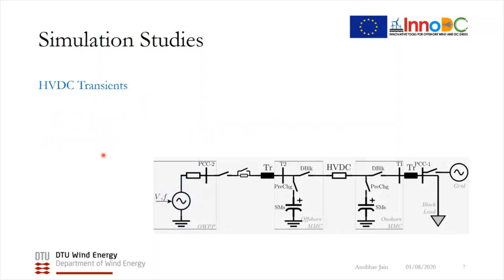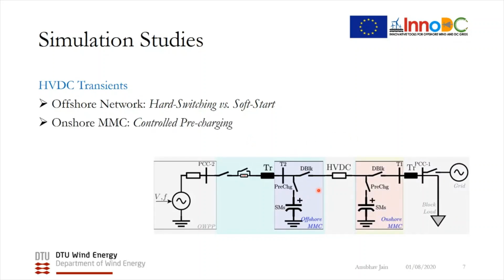Another study that we have performed is to look more on the HVDC transients. So for the offshore network, do a sensitivity analysis for hard switching and soft start cases by changing the PIR and the PIT values, and also for the soft start for the different ramp rate values. And for the onshore MMC, the controlled precharging was implemented to reduce the dip of the HVDC link voltage and to control the transients due to the oscillation of energy between the offshore and onshore MMC cells. And the results of this can be found in the PROMOTION work package deliverable 3.7, and more details have been published, which are under review for the Renewable Power Generation Journal.